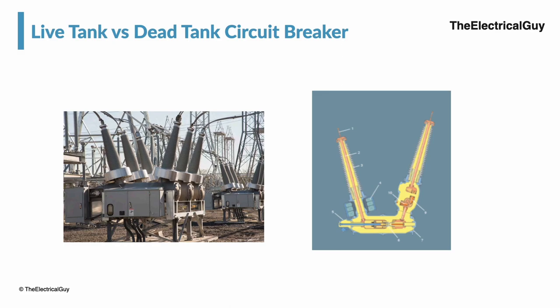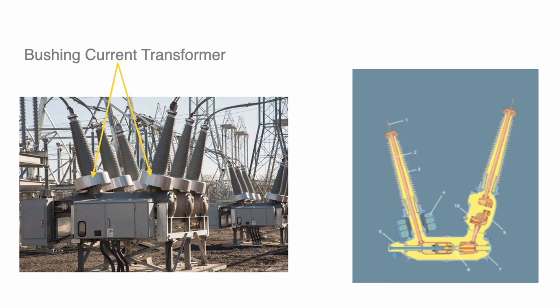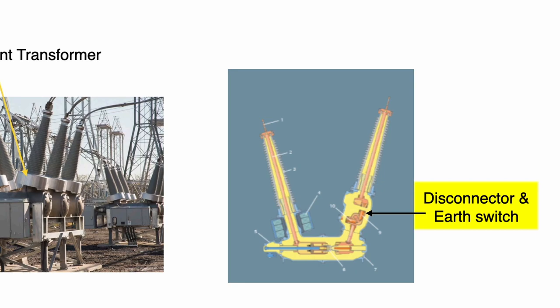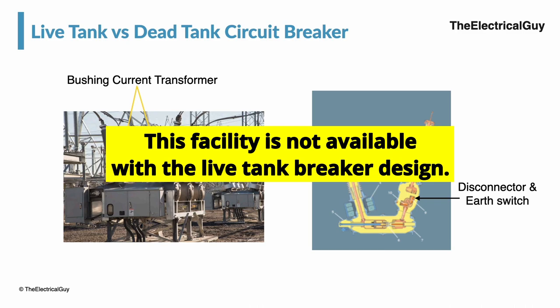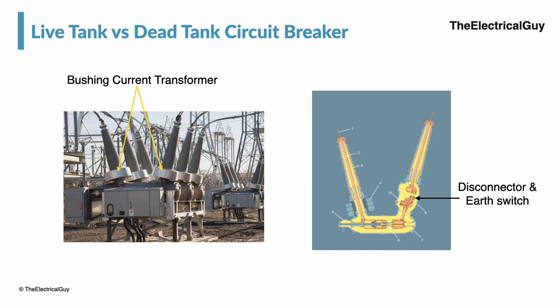The design of the dead tank circuit breaker allows a current transformer to be installed inside the bushing — called a bushing current transformer — and it can be installed in both line and load side bushings. Additionally, a disconnector and earth switch can be combined along with the dead tank circuit breaker, as seen on screen. This facility is not available with the live tank breaker design; you need separate current transformers and a separate disconnector and earth switch.